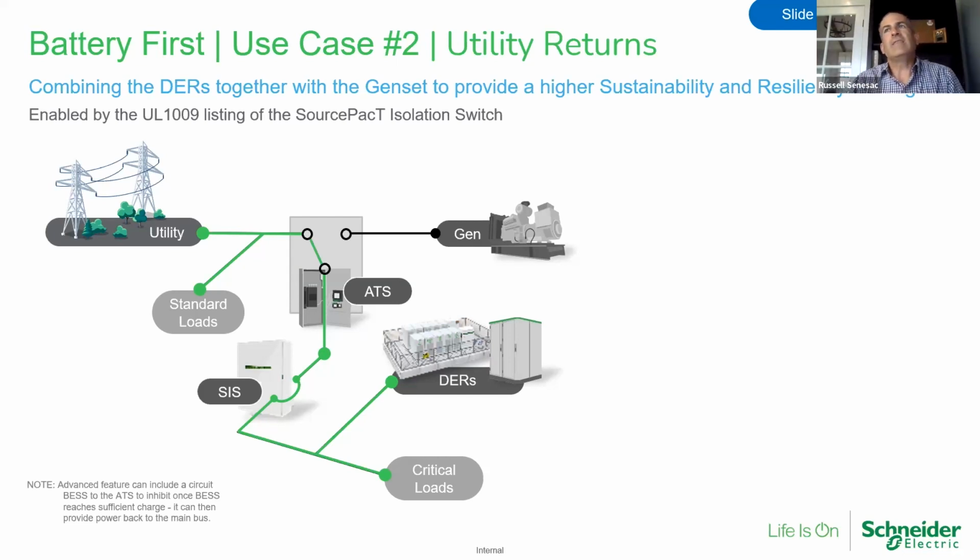So the key thing to take away, to wrap it all up, is that we aren't going to be able to use the same boilerplate spec that we've had for 20 years in these new scenarios, because these batteries are going to require a different approach than just using transfer switches. And it is a great time for us, as we see these new technologies come into play, to update those specifications to take advantage of better sustainability, better resiliency, and provide our customers a better overall solution.